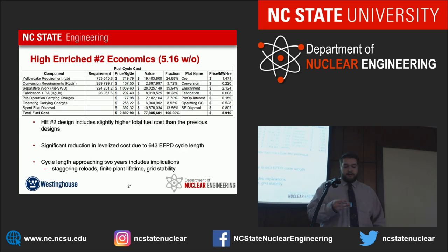Our second high enriched loading pattern naturally includes a higher ore cost and a higher enrichment cost. However, optimizations to the actual distribution within the assembly, our adjustments to our blanket region enrichment, means that we end up with that extra 70 effective full power days, but only an additional $3 million to our fuel cycle cost. And that also means that we see a significant reduction in our levelized cost. It's about a dollar less.